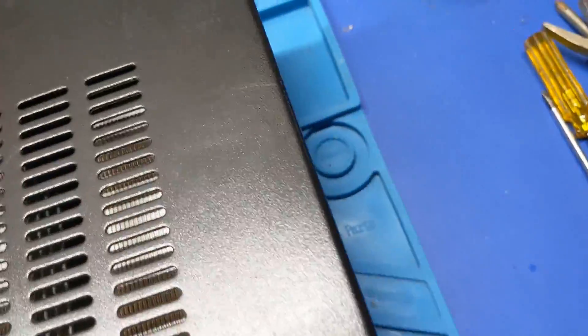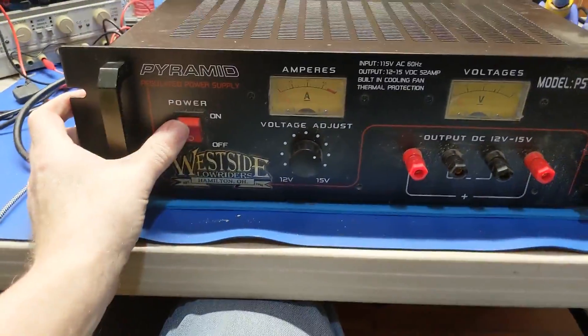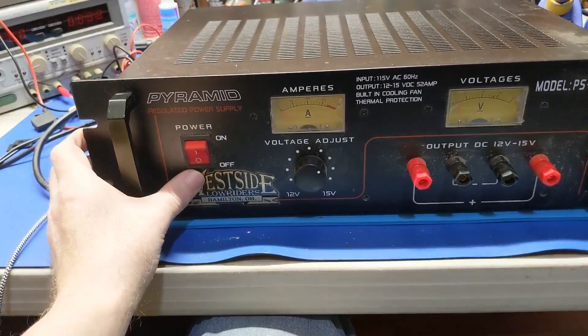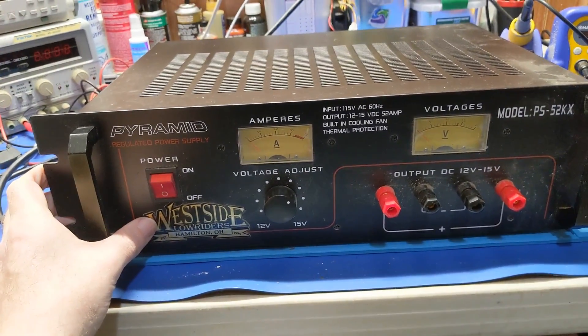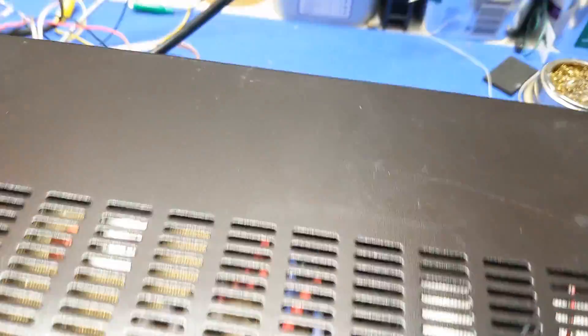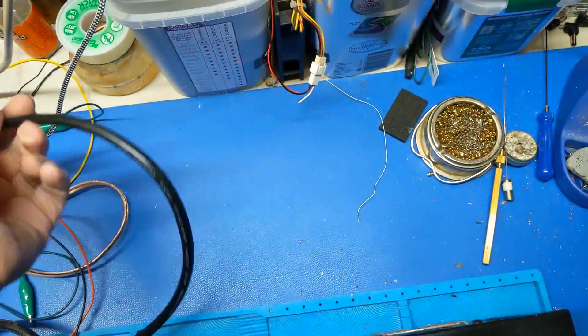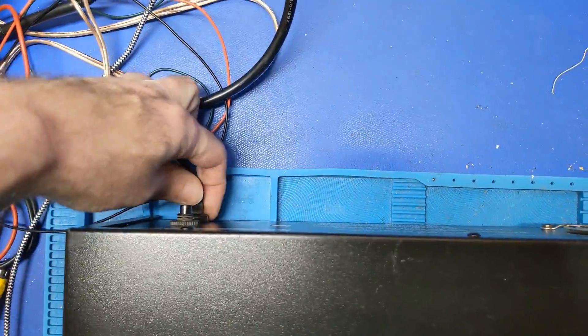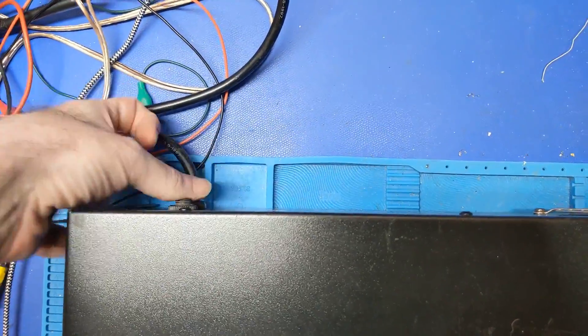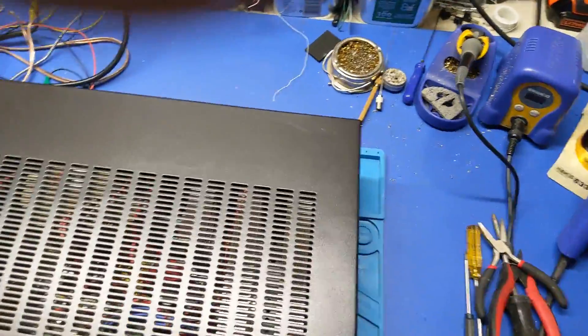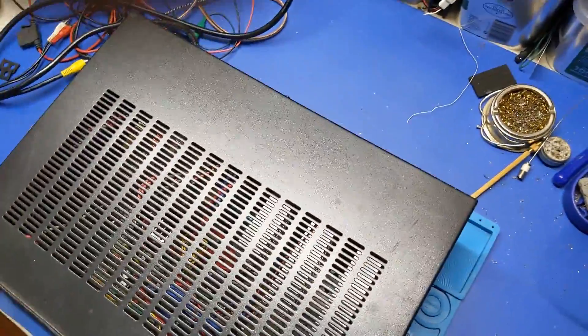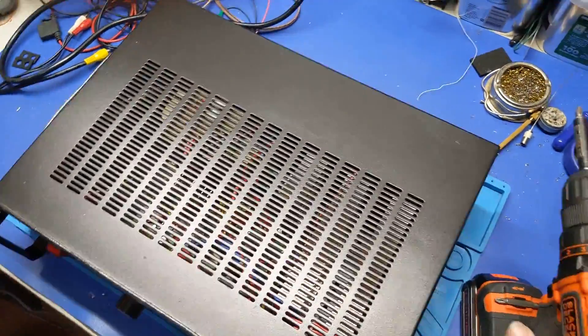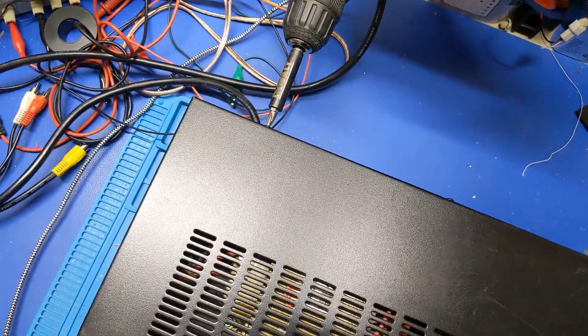Alright let's plug the power in, see what happens. Okay, it didn't like that at all. Yeah, that was, it tripped the circuit breaker. So well we know what the fault is. There is a hard short that dimmed the lights when I went to turn it on.